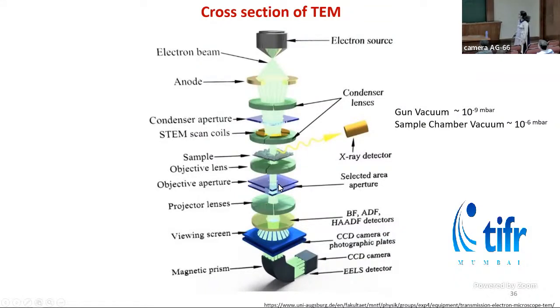magnify the image. There are different detectors like bright field, annular dark field, and high angle annular dark field. So these are the Z contrast detectors in TEM. Here is the CCD camera, which is used for imaging, and the electron energy loss spectrometer sits here. This is the X-ray detector to detect the elements present in the sample. This whole assembly again sits in a high vacuum, where at the gun it is 10 to the power minus 9 millibar vacuum level, and at the sample it is 10 to the power minus 6 millibar vacuum level.